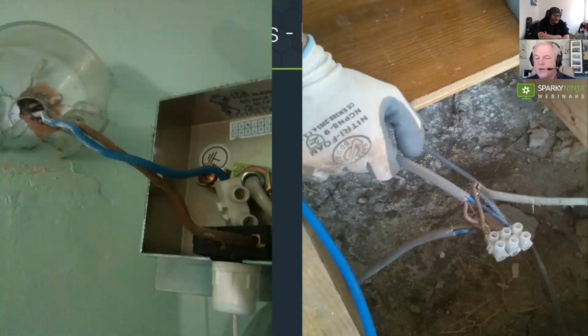So those terminals could become loose. If they come loose, they could start to arc. Okay. If they start to arc, we've got a fire risk. It's underneath the floorboards, which are wooden. Okay, so you've got combustible material. Nothing around those connections. So the connections need to be enclosed, and they need to be a maintenance-free connection.